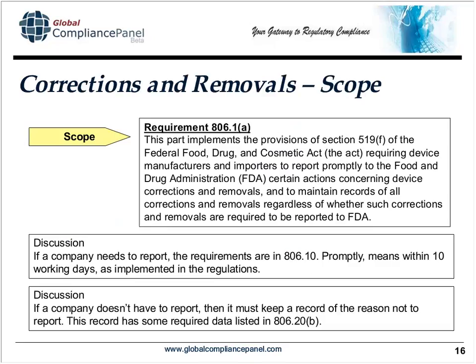Let's start with the requirement, which comes from Part 806 — this is one of the less well-known parts of the regulation. The regulation implements provisions of the Food, Drug, and Cosmetic Act related to corrections and removals. If a company needs to report, the requirements are in 806.10 and they must report promptly, defined as 10 working days. Sometimes you don't have to report — there are exceptions for corrections or removals not requiring FDA notification — but then you must keep a record explaining why you didn't report. That record has specific required data elements found in 806.20(b).